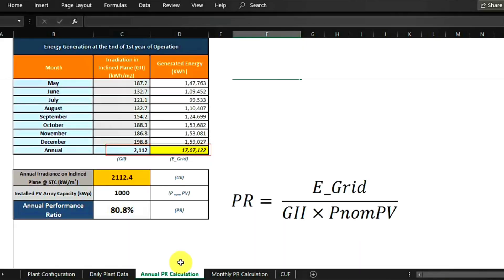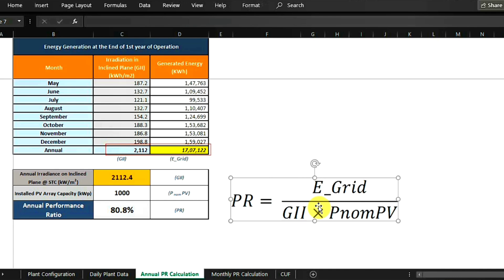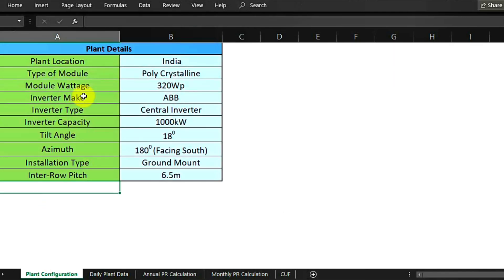Let's check out how to do the calculation using the Excel sheet. This is the Excel sheet for PR and CUF calculation. Here you can see the tab for Annual PR Calculation. The formula mentioned earlier is projected here — energy produced and injected into the grid, divided by global irradiance (inclined radiation), multiplied by the DC capacity of the power plant. The first tab shows the plant configuration.